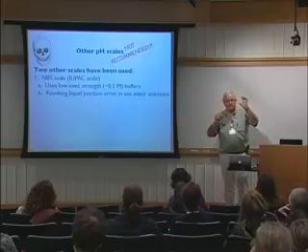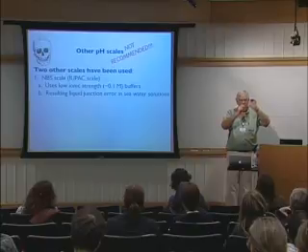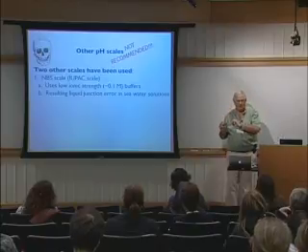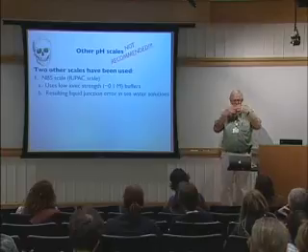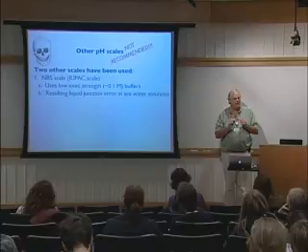which means that that liquid junction between your chloride solution in the electrode and your actual sample changes when you move from the buffer to seawater. And so there's an added uncertainty in that because you don't know how much it changes. It depends on the design of the liquid junction.